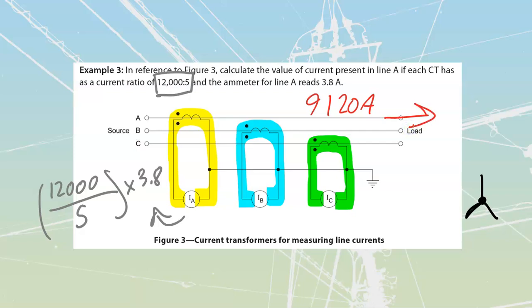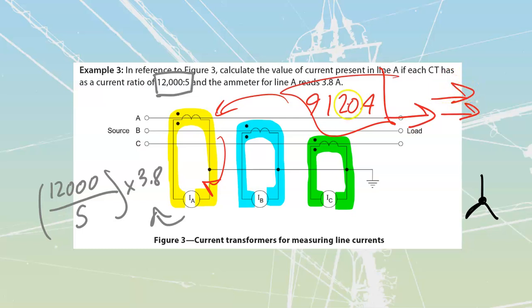Remember, it is my load that is in charge of pulling this current. And this current, as it flows through the CT, is what's generating this one over here. This device, this CT, and this ammeter here is not seen as a load to the system. It is just governed by the system itself. Ultimately, it is the amount of current flowing out to the load over here that determines the line current, which then determines this.